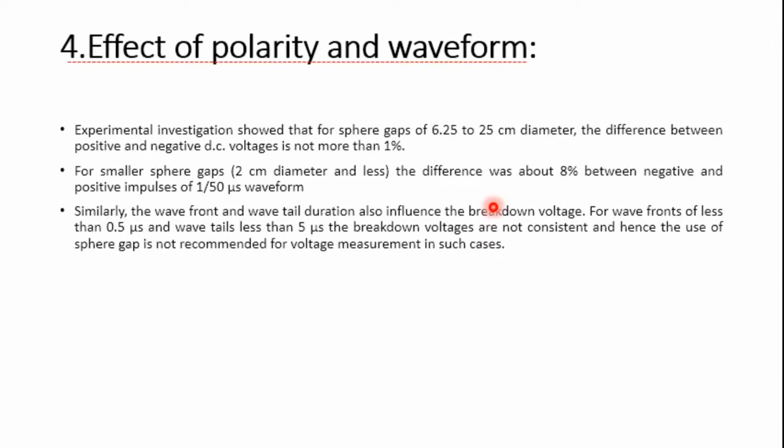However, there is a difference of 8% between the negative and the positive polarity in the case of the 1/50 microsecond impulse and a 2 centimeter diameter or lesser. Generally in our laboratory conditions, polarity does not play a very important role. However, we can observe a small change in the values across the positive and the negative polarity. Again, it mainly depends upon the temperature, pressure, and all the parameters.